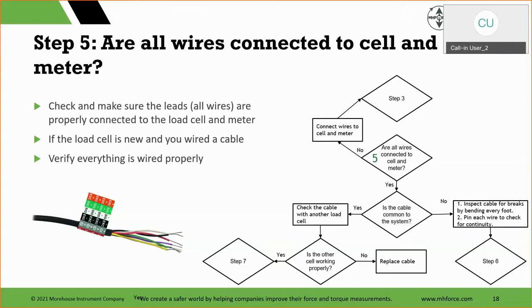The harder one is the intermittent problems. So if you're calibrating a load cell and all of a sudden numbers are kiting or jumping on you when you move it, chances are you have a connection that is problematic, right? You have a break in the cable that is shorting or is coming open. More than likely it's coming open. Load cells very rarely short unless there's something major that's shorting both lines. But more than likely a cable's been nicked.